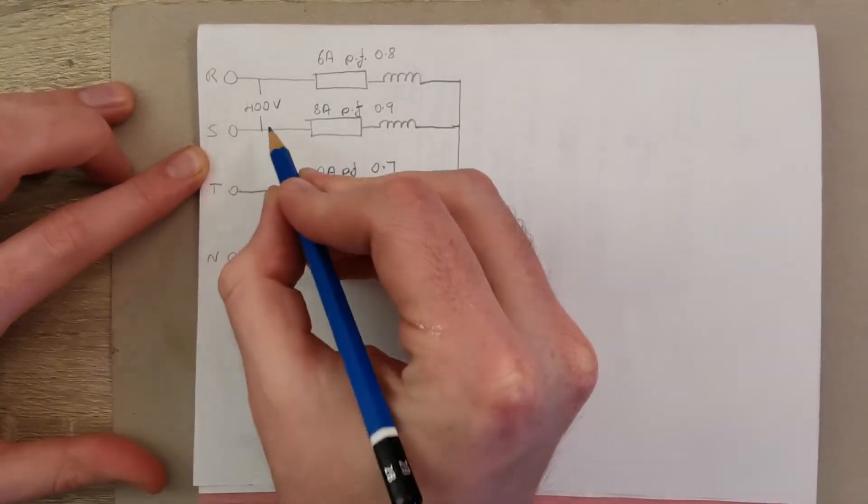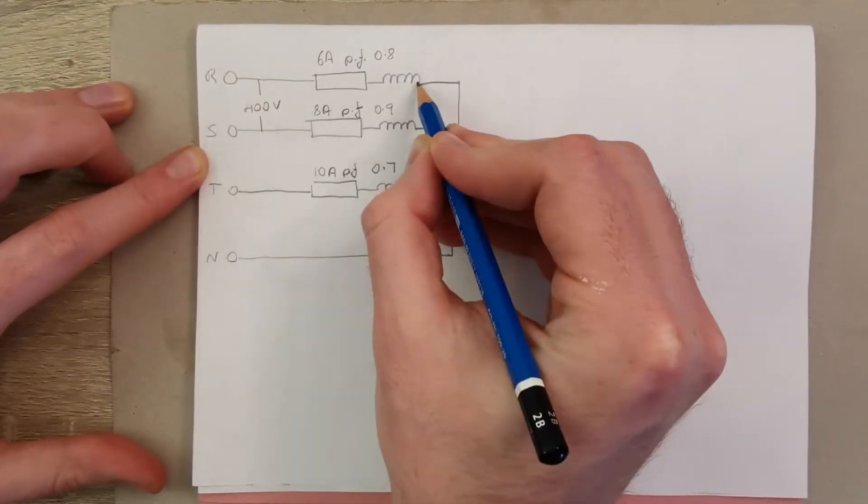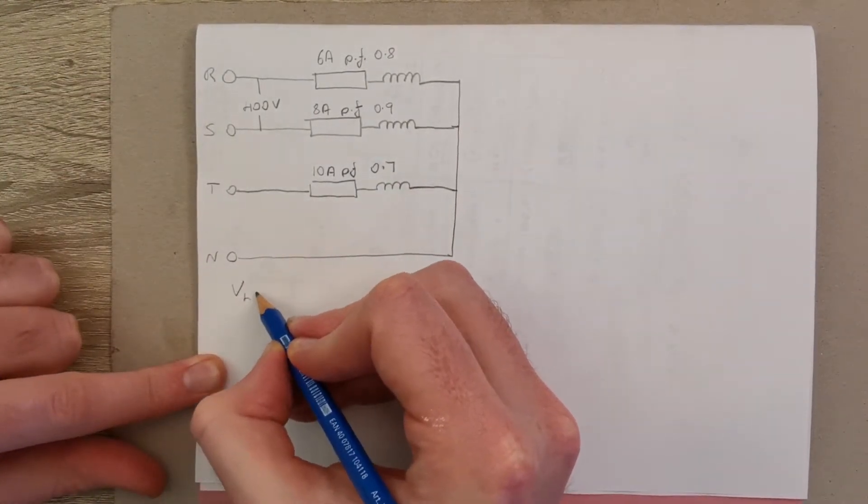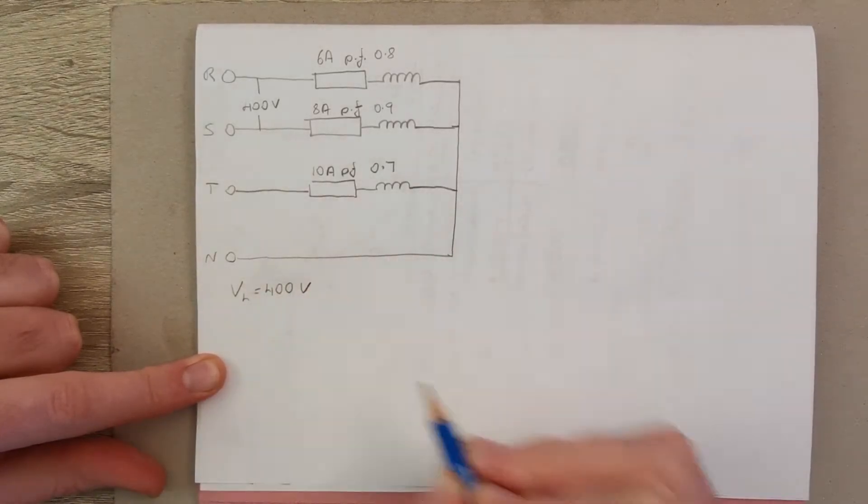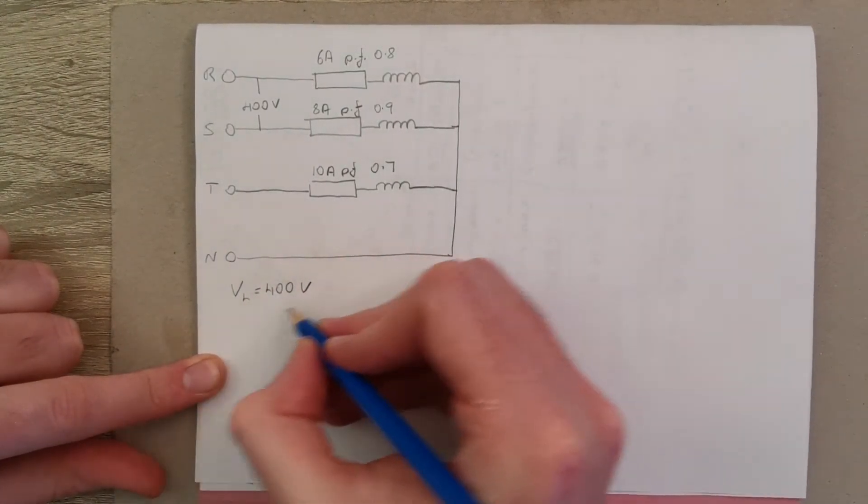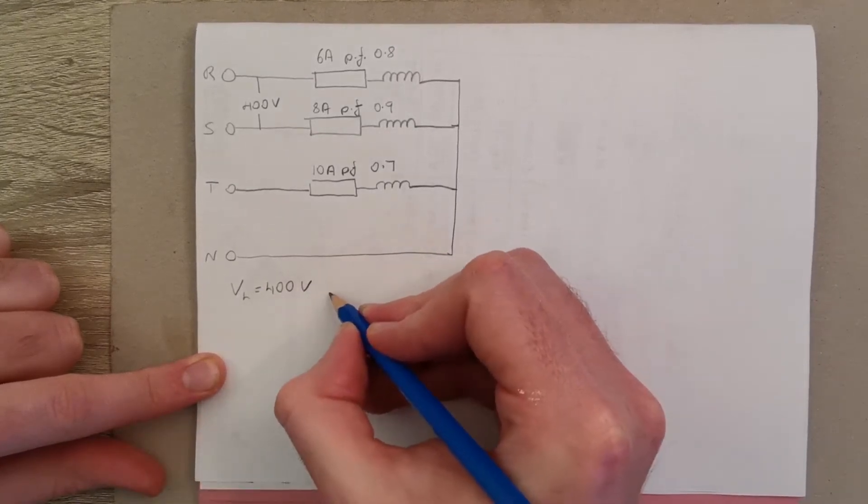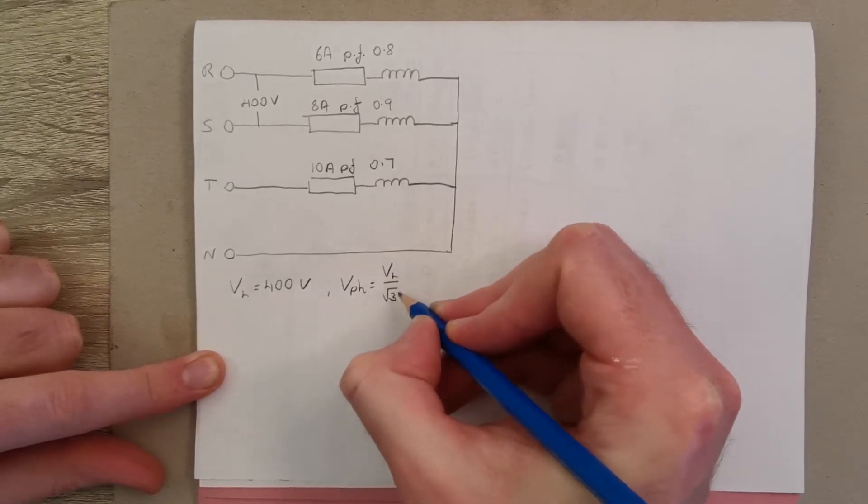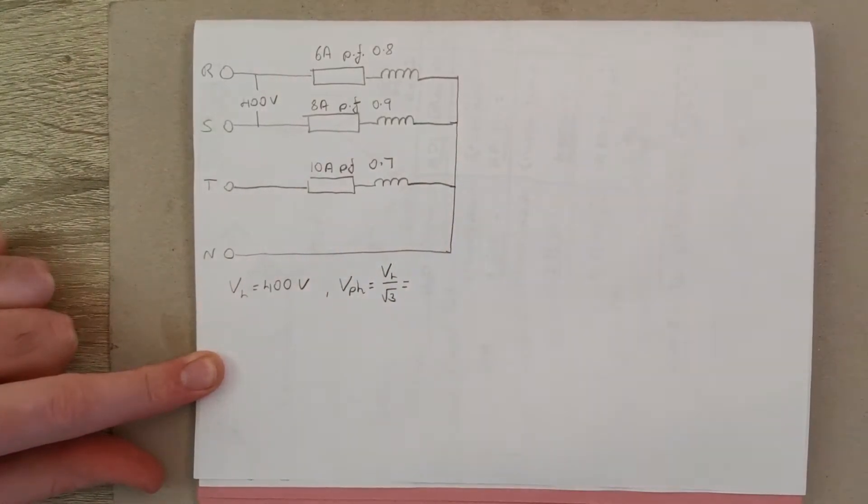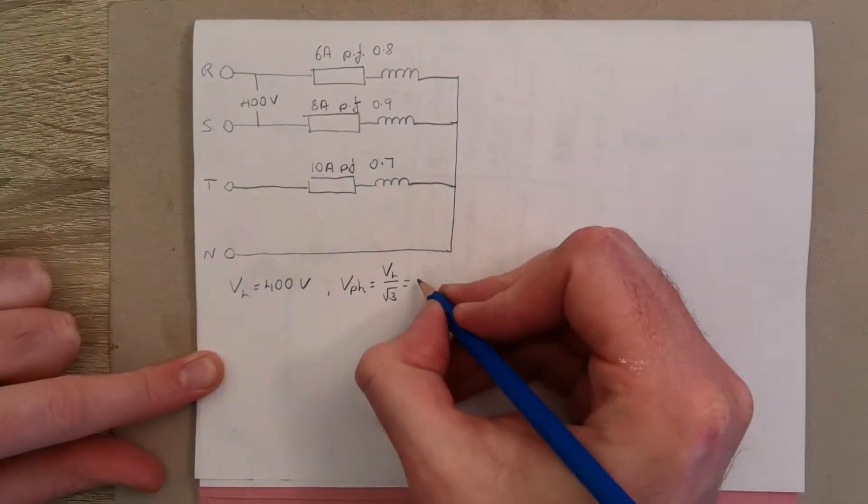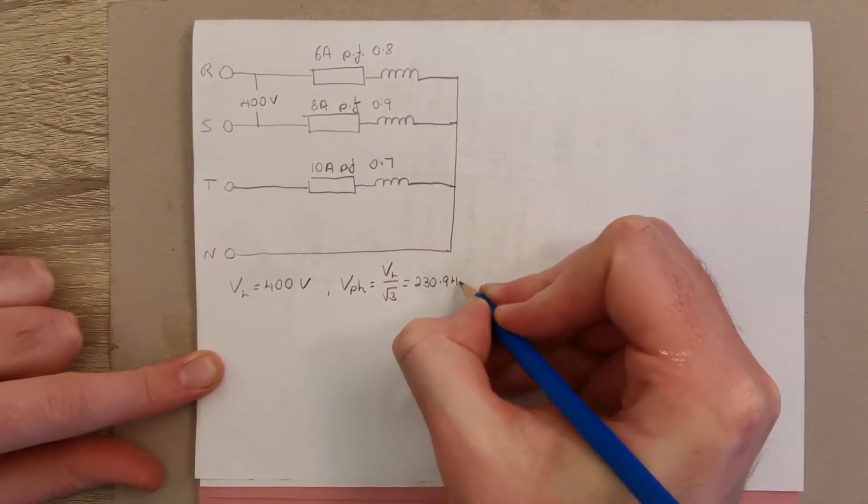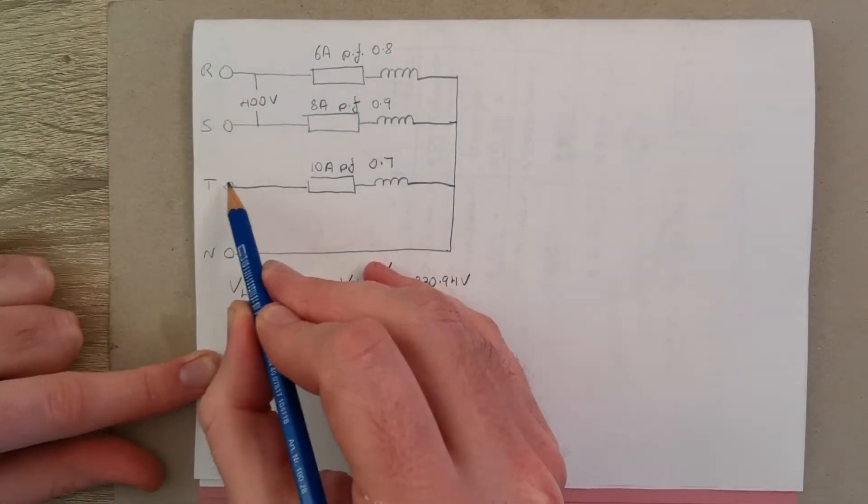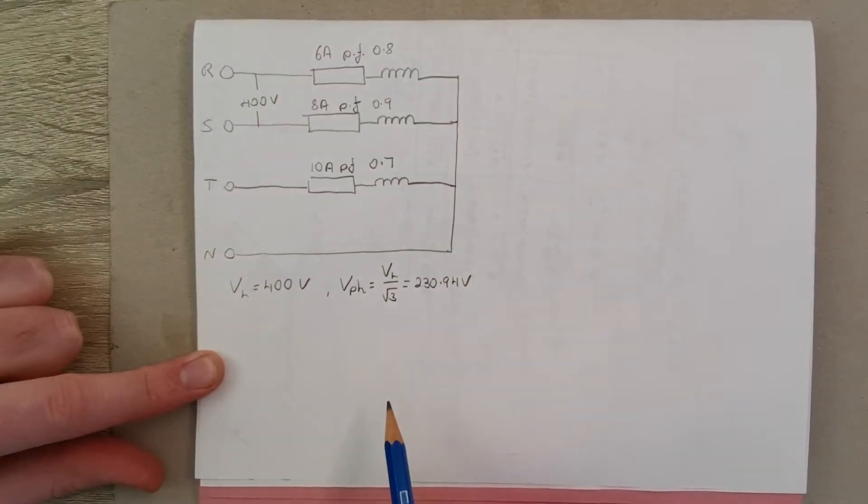First thing we need to do is work out, well if this is the line voltage, what would be the phase voltage across each phase? Well we know what the line voltage is, 400 volts, and then we can work out our phase voltage because that will be our line voltage over the square root of 3, and that works out at 230.94 volts. So that's the voltage across any phase at our star point or our neutral.